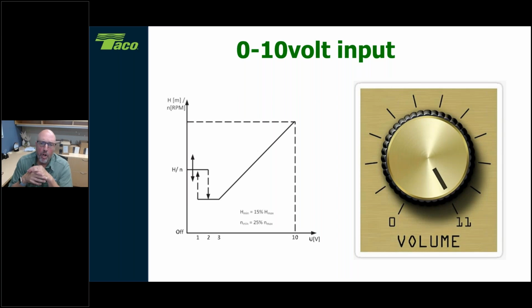Another mode that we're going to have built into this circulator that is probably one of the more common functions, like that twin pump, which is probably by far the most popular. 0 to 10 is now another control feature that we have built in here, where we're going to have a signal from something else to tell us what speed to run at. So there's going to be an advanced building management system that's going to tell us what to do. You might have that opportunity, like I show in the picture here. Hey, 10's not enough. I need it to run to 11.